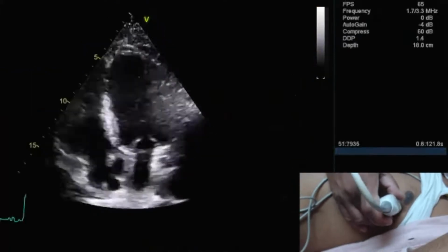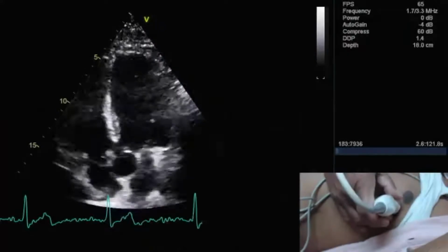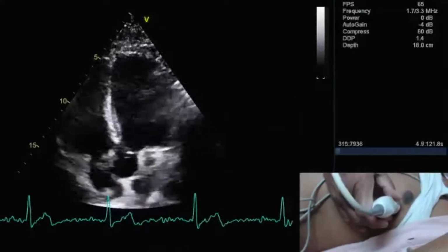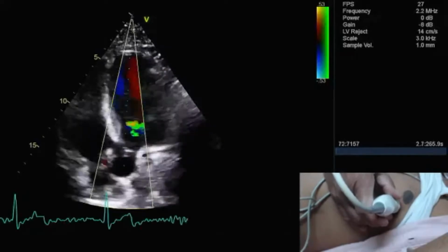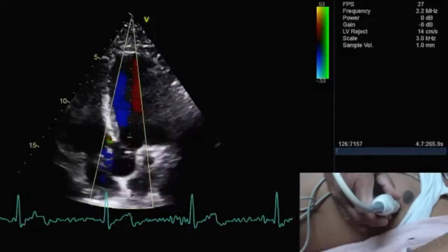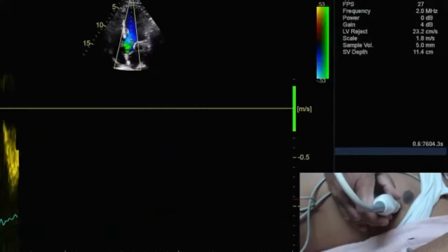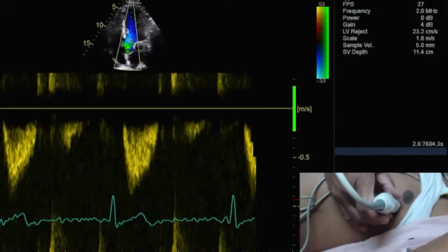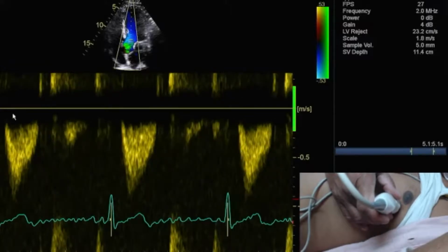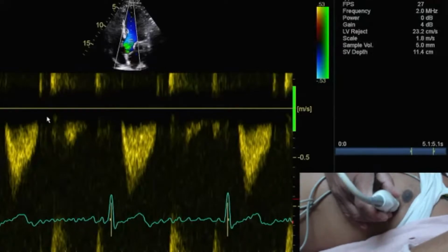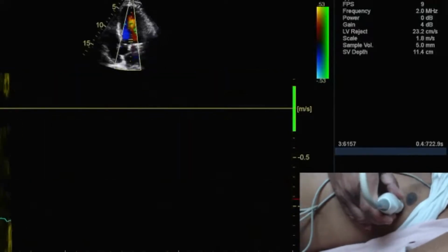If you show the pulse Doppler, they can see the high filter has been kept so high that you cannot see the base of the pulse Doppler. Okay, sir, I'll show them again, so that they should know how to use the filters. You see, now you see what Dr. Prash's study is showing. This is where the baselines are cut completely. To get rid of this, I have to reduce my filter.